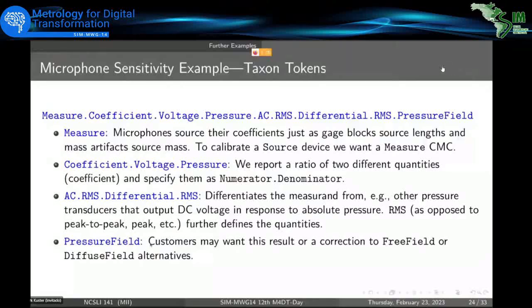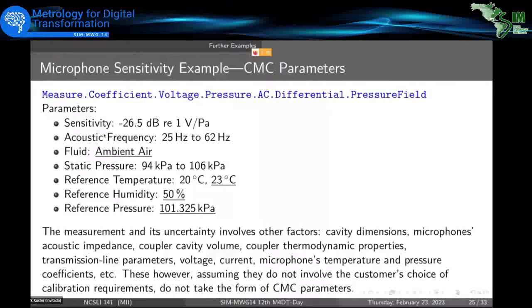We also specify parameters such as the nominal sensitivity of the microphone, the primary parameter, as well as the influence and input quantities: frequency, pressure range, etc. Now there are a number of other factors that go into any calibration, in this case like cavity dimensions, impedance, and various other parameters. But those typically are not something that the customer selects a service from. They're just internal details to the process, so they don't become part of the CMC template.